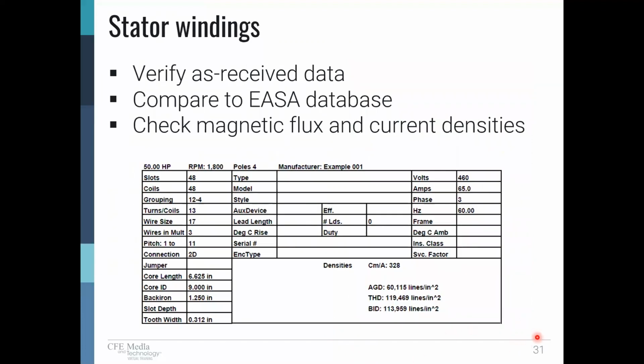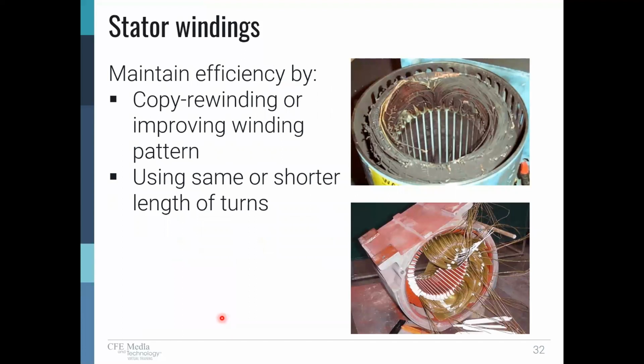And as an example, and again, I'm not going through this card, we show a display of the output from a winding verification, but it gives us all the elements of what the winding design is about, what the characteristics of the winding are. And over here, we've got these magnetic flux densities that tell us whether or not it's a reasonable value. And we can verify the data. If it's a service center that belongs to EASA, they have access to our database of over 250,000 windings on file that they can compare what they found in that motor to it. If it's not on file, they may have a program like this to check magnetic flux densities, or as an EASA member, they can call us in our technical support group and have us check the data for them.